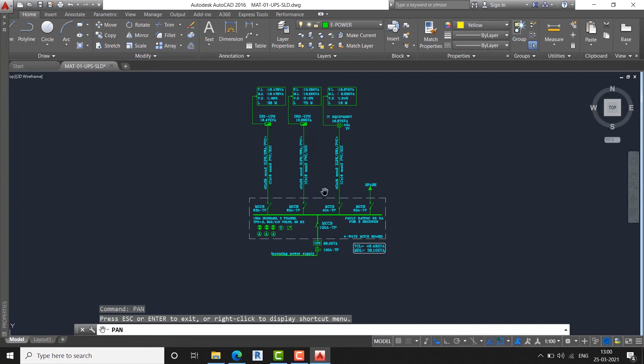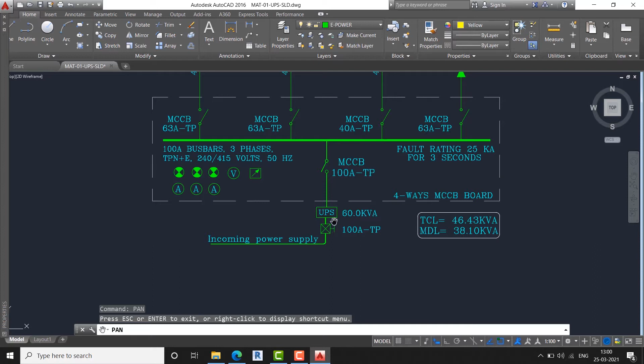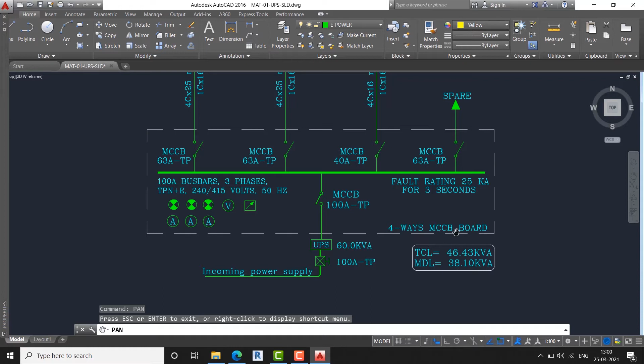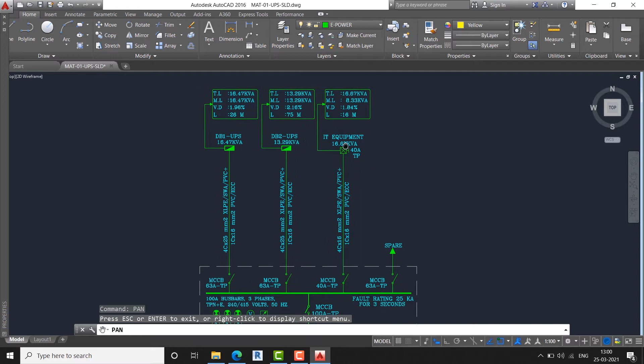This is a single line diagram. Here it's showing the incoming connected to the isolator, 100 ampere rating, and the outgoing connected to the UPS system, which is 60 kVA. The outgoing from the UPS is connected to the 4-way MCCB board. This panel has 4 outgoing feeders, one is spare, and these 4 outgoing feeders through cable are connected to one small DB, and the DBs go to the emergency system.